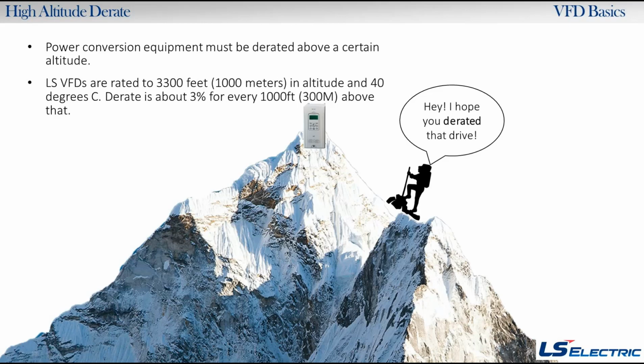So it's a pretty simple formula. You just need to reduce your current rating by 3% for every 1,000 feet. But we also have a little Excel sheet that calculates this for you, so you can plug in your altitude and it'll tell you what your derate is. Okay, so when we say derate, you're going to oversize the drive to compensate for that derate.